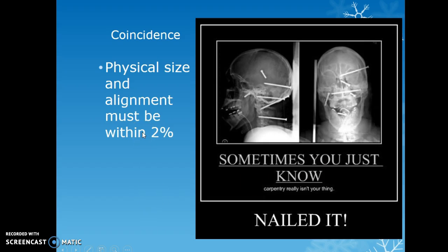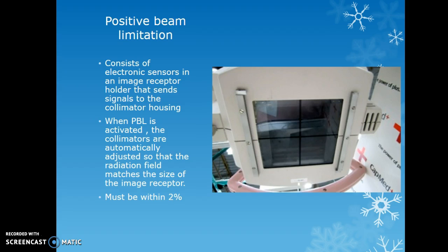Coincidence means the physical size and alignment of the light field must be within 2%. What you visually see on the table should match your output on the final image. Positive beam limitation uses electronic sensors in the upright bucky and table bucky to detect the cassette size and send a signal to the collimator housing to automatically close the shutters to that field size. This must also be within 2%.